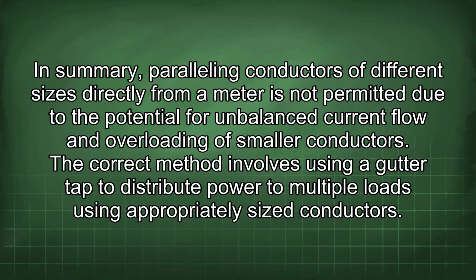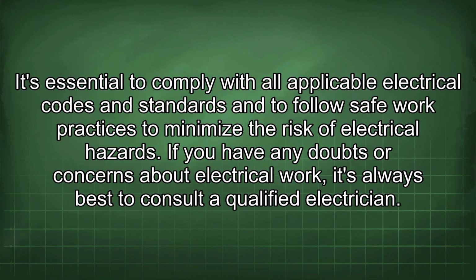In summary, paralleling conductors of different sizes directly from a meter is not permitted due to the potential for unbalanced current flow and overloading of smaller conductors. The correct method involves using a gutter tap to distribute power to multiple loads using appropriately sized conductors. It's essential to comply with all applicable electrical codes and standards and to follow safe work practices to minimize the risk of electrical hazards. If you have any doubts or concerns about electrical work, it's always best to consult a qualified electrician.